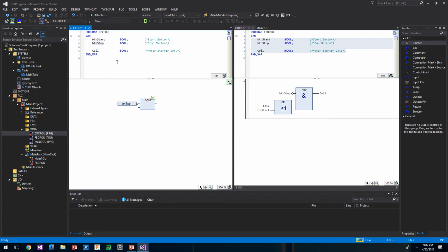You may or may not need to do that, obviously, depending on whether you're using normally closed or normally open contacts on your button. I'm a big advocate of using normally closed on stop buttons, but in reality, it really doesn't matter that much, especially if you have a safety system, like a true dual redundant e-stop system. That's really the only thing that's required to be a certain way. A lot of the machines that we build at work, the stop button is just normally open, because of the style of button we use, it's cheaper, and we only have to stock one type of contact. And then the e-stops are a completely different thing. Those e-stops are very, very critical that they be wired a certain way. So for the sake of this argument, we're just going to say it's a normally open button.